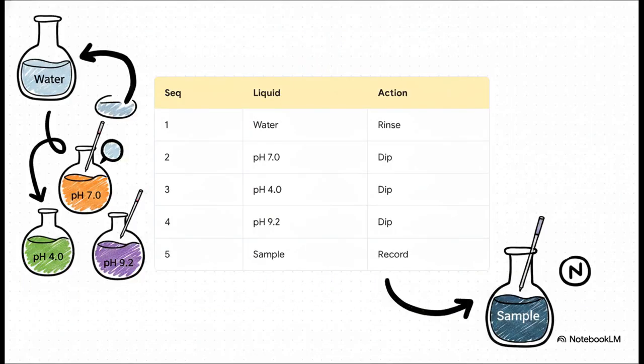So let's review the whole shebang. The exact sequence is strictly locked. Distilled water to rinse and blot, pH 7.0 buffer to dip and stabilize, then the 4.0 buffer, then the 9.2 buffer, and only then your sample solution to record the pH. Altering this sequence literally alters your truth in the lab.